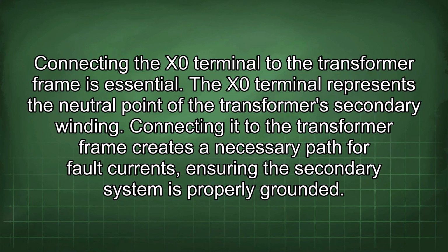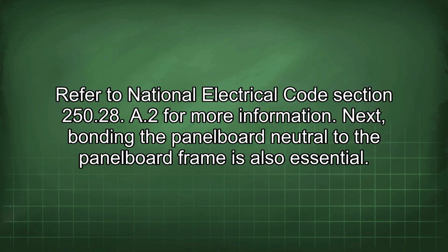Connecting the X0 terminal to the transformer frame is essential. The X0 terminal represents the neutral point of the transformer's secondary winding. Connecting it to the transformer frame creates a necessary path for fault currents, ensuring the secondary system is properly grounded. Refer to National Electrical Code Section 250.28 A2 for more information.